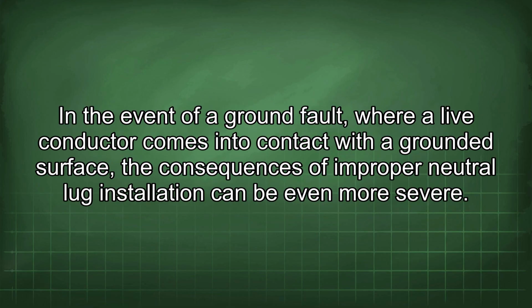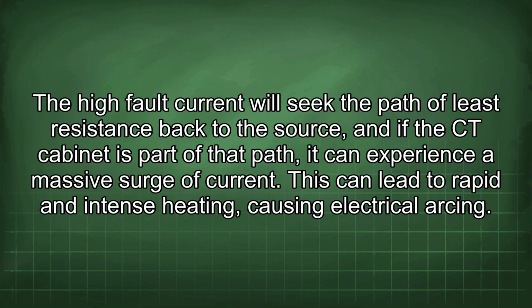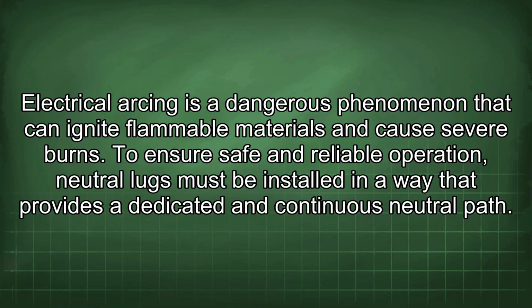In the event of a ground fault, where a live conductor comes into contact with a grounded surface, the consequences of improper neutral lug installation can be even more severe. The high fault current will seek the path of least resistance back to the source, and if the CT cabinet is part of that path, it can experience a massive surge of current. This can lead to rapid and intense heating, causing electrical arcing. Electrical arcing is a dangerous phenomenon that can ignite flammable materials and cause severe burns.